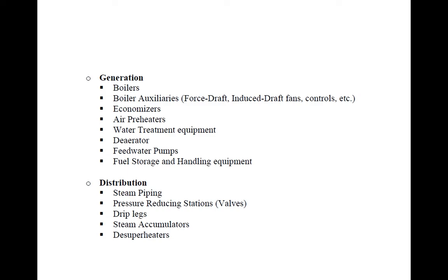the boiler feed water. So for example, if the feed water is 20 degrees Celsius when it enters the economizer, at the output of the economizer it can reach a temperature of more than 100 degrees Celsius.